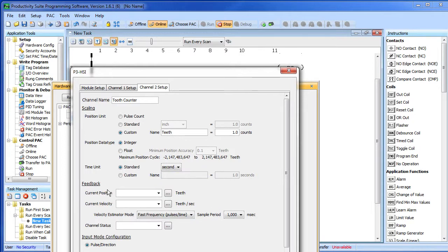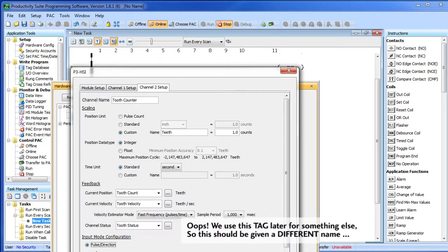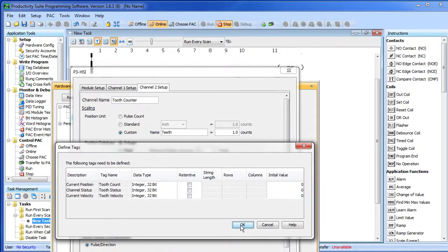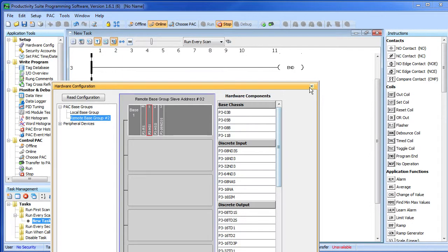Our current position is really a count of teeth so we'll call that tooth count – note the units are all set up for us – and our velocity will be tooth velocity. Again, the units are all set up. Finally, tooth status is our status. We're counting pulses – this isn't an encoder – so we want to make sure that pulse and direction is selected, and we're done. So all we did was name the channel, change our units, define some tags and make sure we're counting pulses. Hit OK, let the Productivity 3000 create the tags for us, and close the hardware dialog.